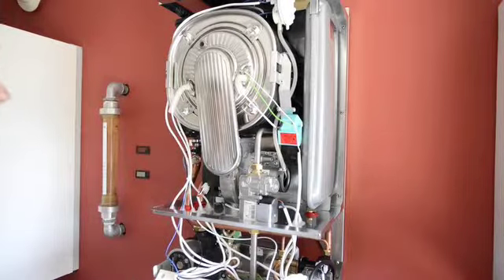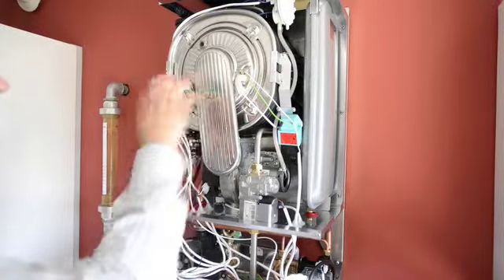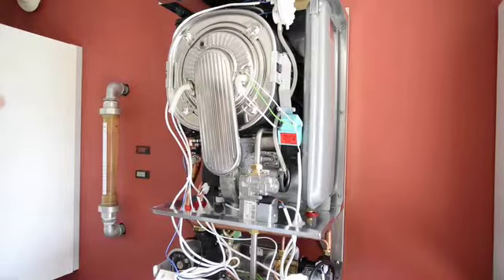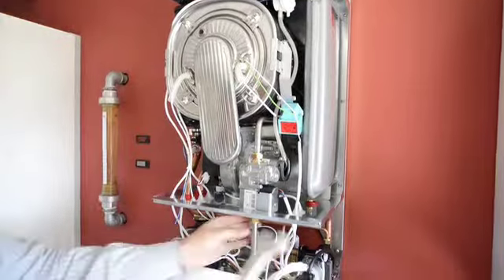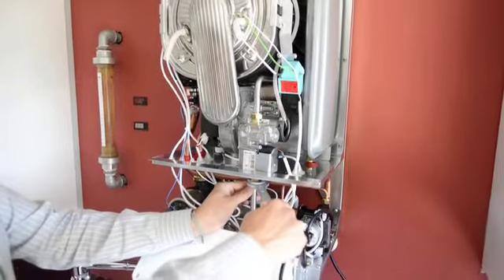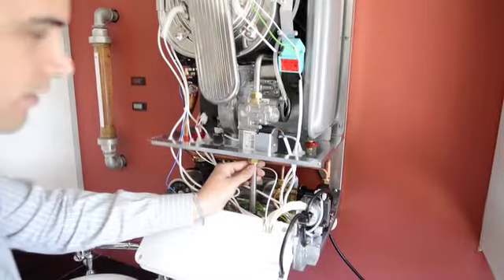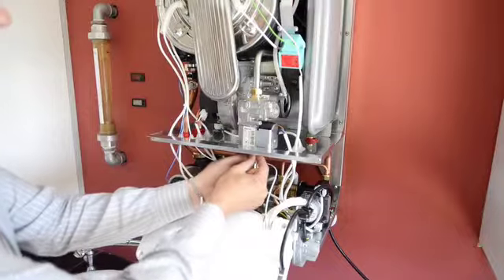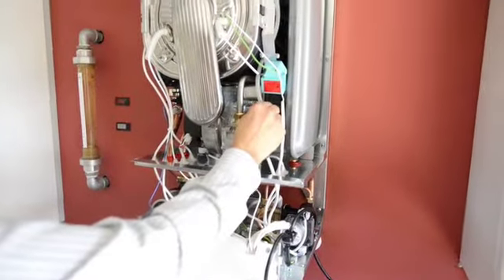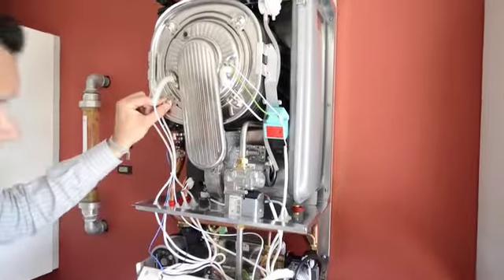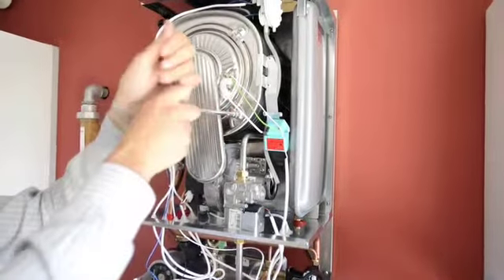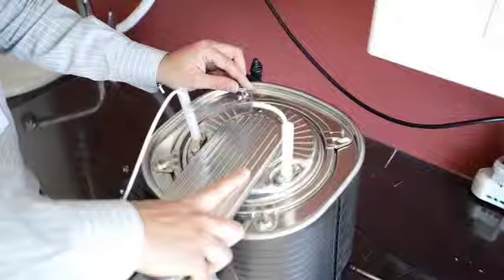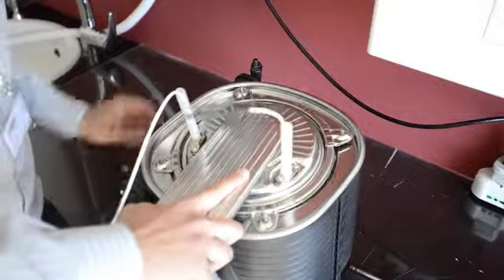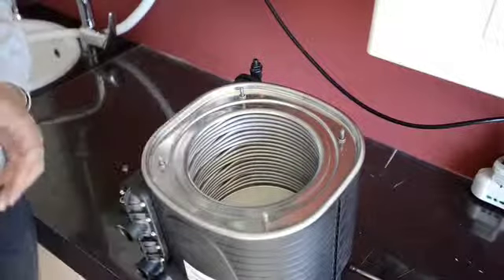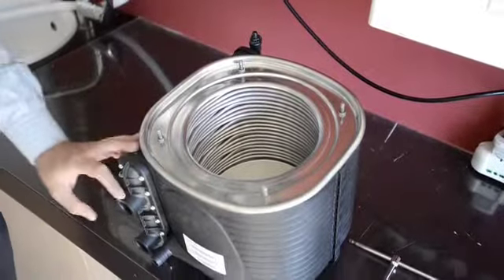Another very important operation to be done periodically is the cleaning of the interior of the heat exchanger. To proceed with the cleaning, it is essential to loosen the gas valve, dismount the 2 screws below, remove the tube attached to the pressure gauge, and loosen the 4 bolts. Once we have removed the full 4 bolts, we can remove the burner and we can proceed to the cleaning of the interior of the heat exchanger.